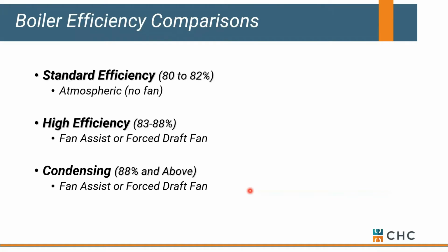Let's jump into efficiencies real quick. This is always an interesting topic. We looked at our gas barbecue on our back deck, an atmospheric boiler. It's typically 80 to 82%. Another way to look at this, you're sending 20% of your energy right up the vent pipe. Okay, so not very friendly on the gas meter. If you're looking at a high efficient, these would be a non-condensing boiler, you're going to get those up to about 87, 88%, which still means you're sending about 12% of your energy right up the vent pipe. Okay, if you're looking at a condensing boiler, you're typically talking about efficiencies that are 90% or greater.